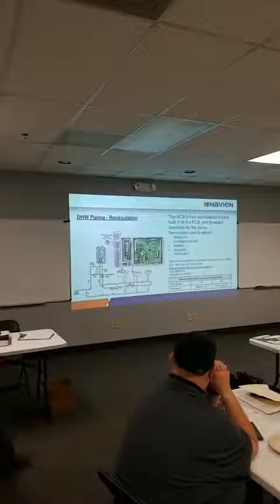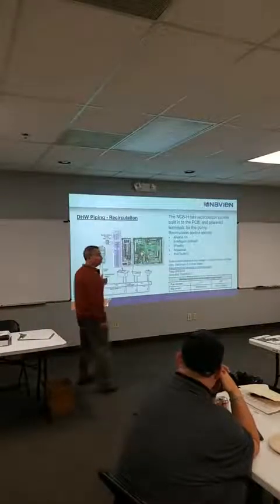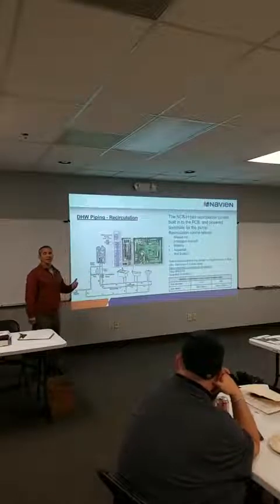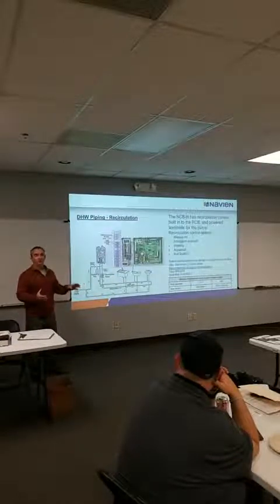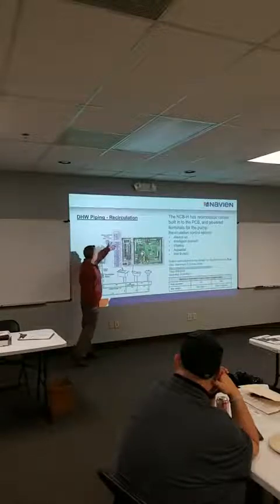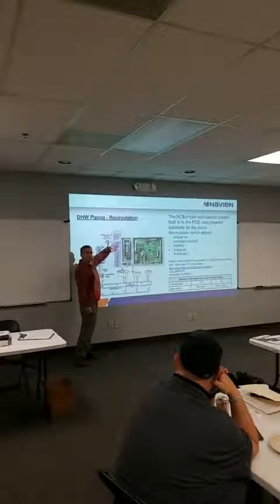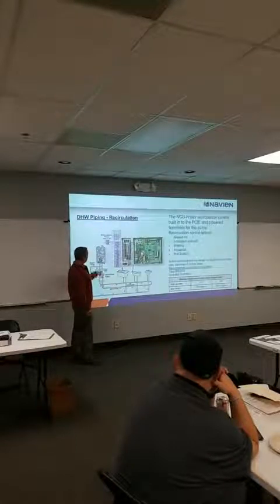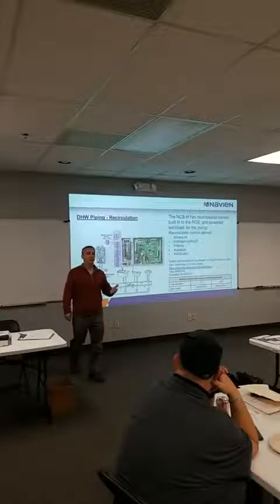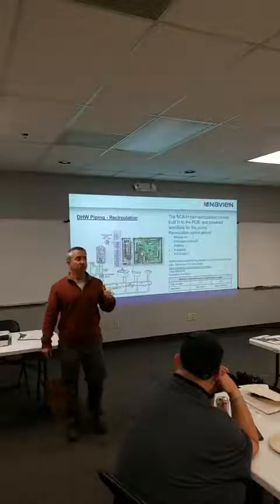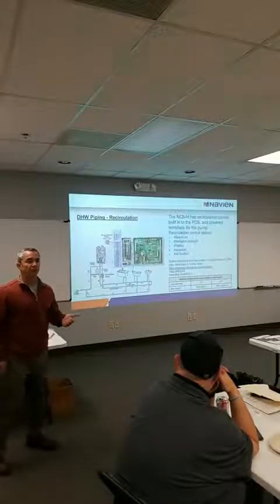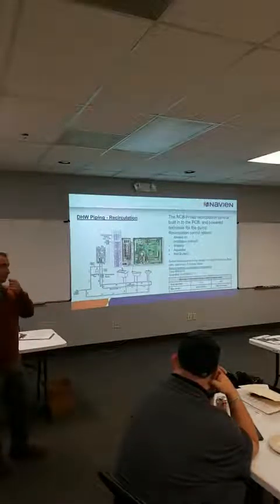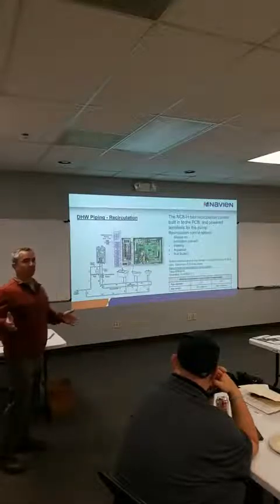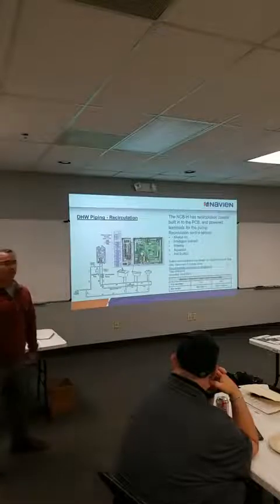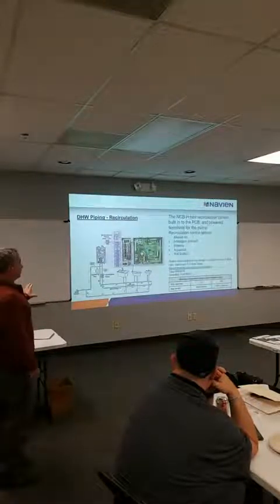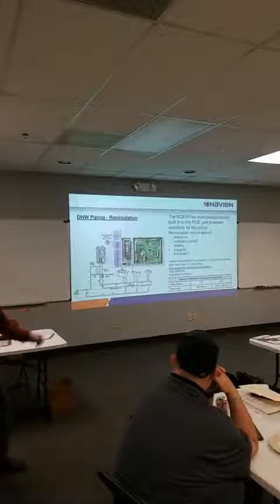The domestic setup's the same. Another thing that we added to this unit: a lot of people like to do domestic hot water recirculation. With the old combi, you had to buy a bunch of controls and wire it in. This time, we're giving you power for your pump, so you can now pipe in an external pump. We'll power that pump, and we're including recirc programming in this board, just like our tankless water heater that comes with recirc operation. You don't need any third-party controls. So what Navien's trying to do is eliminate as many third-party vendors from trying to run their equipment as possible and run it on our own. So it's a substantial upgrade. It's what people have been asking for since we came out with the combi.